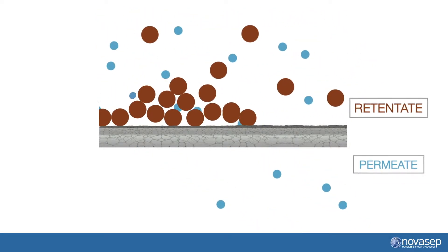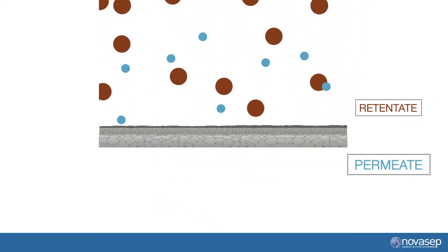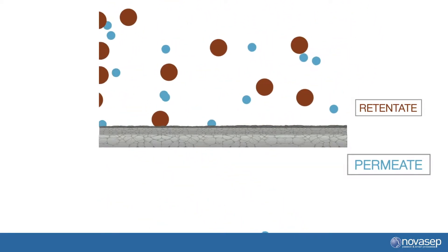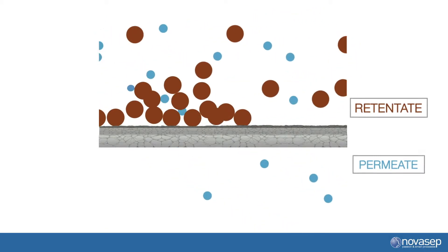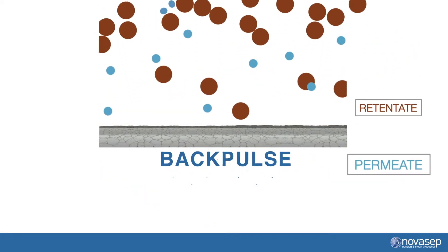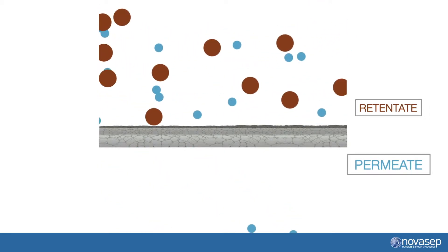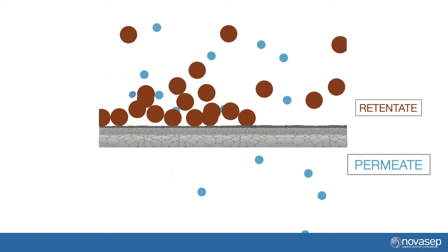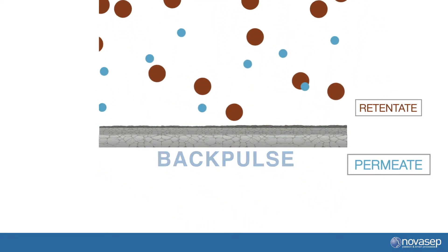Decreased flux can be compensated by increasing the TMP, but this will often work only for a short period of time before you need to clean the membranes. Another method is to apply a back pulse, meaning a short period of TMP inversion where permeation occurs in reverse. Back pulsing removes part of the resistance due to fouling and therefore restores permeation flux performance without cleaning. CIP frequency can be greatly optimized by incorporating back pulsing.